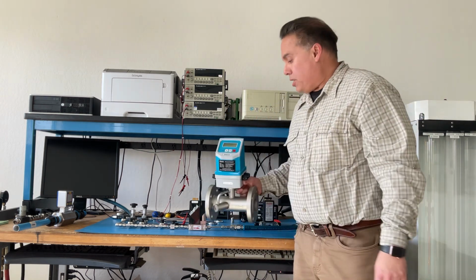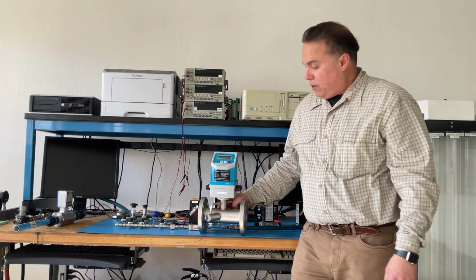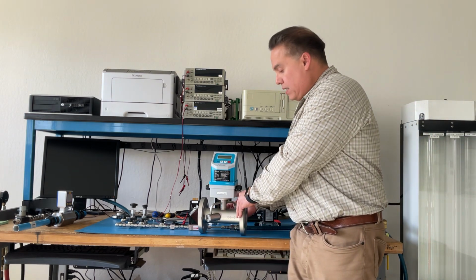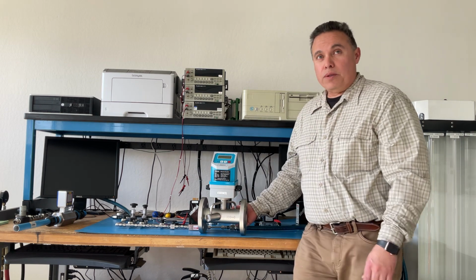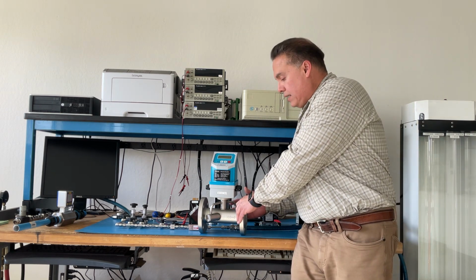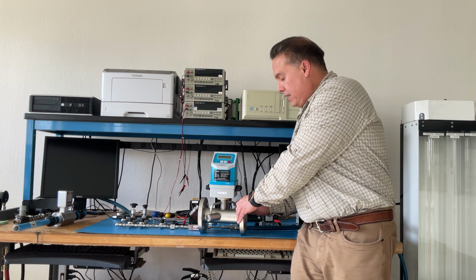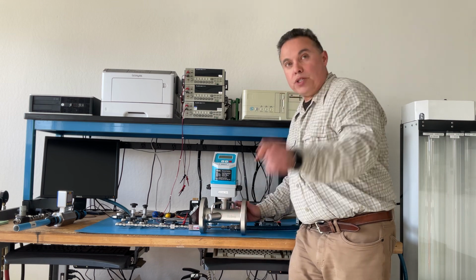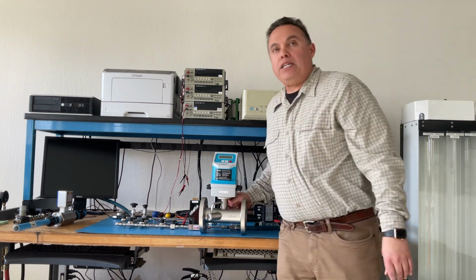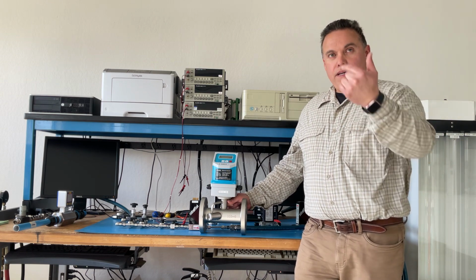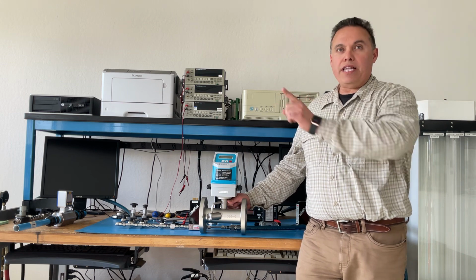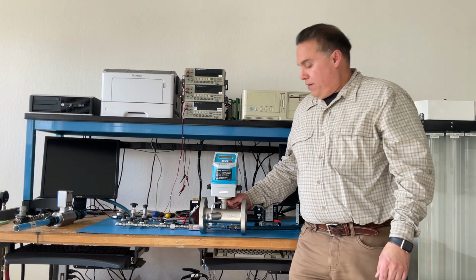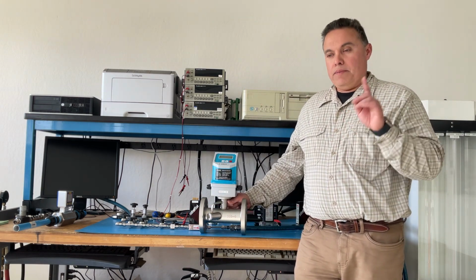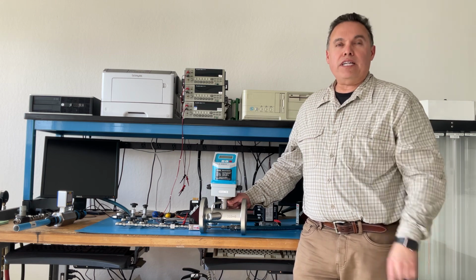You measure the time it takes for sound to travel from this emitter to this receiver. And what it will do is it will also shoot back a signal from the back transmitter to the front receiver, so it'll alternate. And it will measure the difference in transit times of this transmitter shooting this way and this transmitter shooting that way.